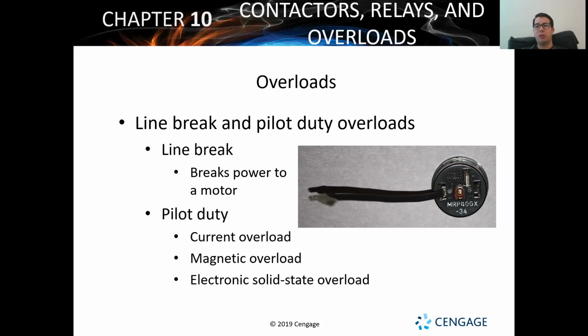HVAC equipment requires extreme amounts of electricity. Because it's going to require that high load, and it's going to cost so much to operate and repair, to avoid major repairs we include these kinds of safeties to make sure that the system's operating at least under somewhat ideal conditions. For a fuse, hey, it's not pulling too much amperage. Cool. But what about temperature? What about voltage? What about magnetism? That's when we're looking at these other types of overloads.